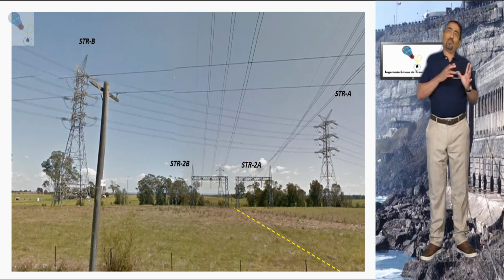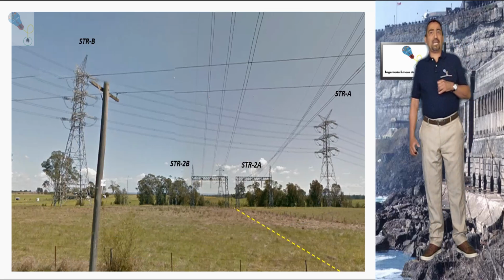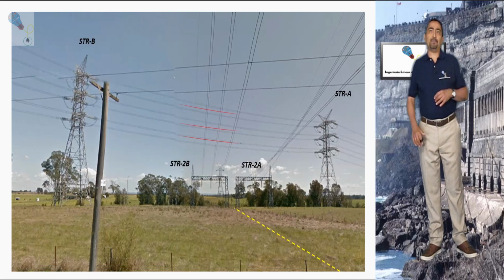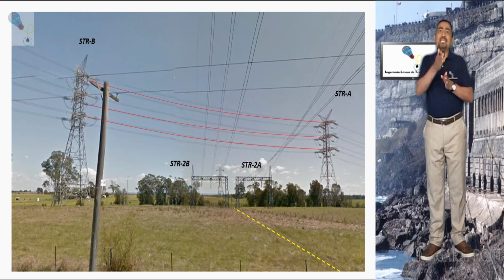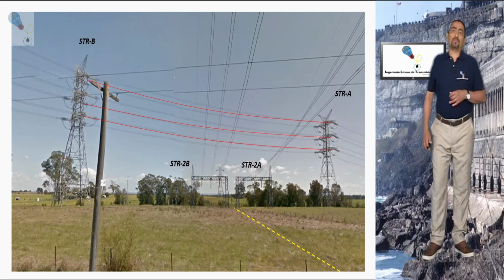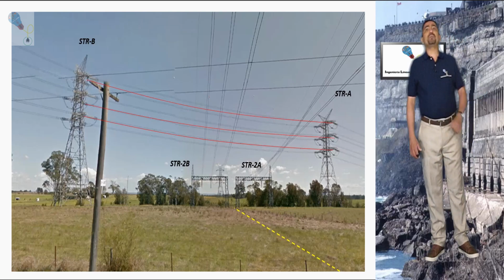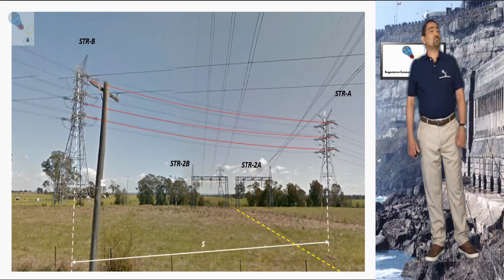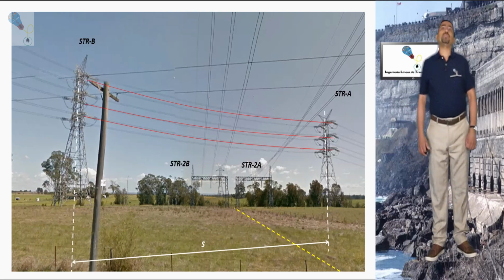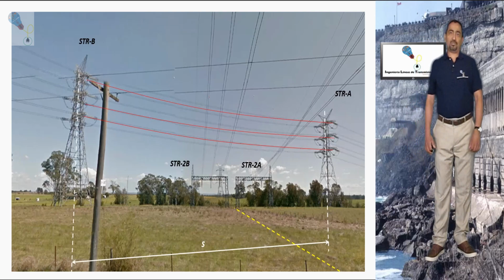Number five: we need the reading of the cable sags or heights of all cables involved at mid-span. Number six, very important: ambient temperature. Also very important, number seven: we need the date and time of the survey.